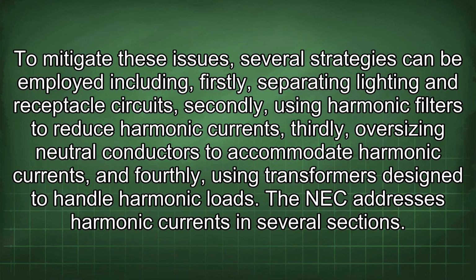To mitigate these issues, several strategies can be employed, including, firstly, separating lighting and receptacle circuits. Secondly, using harmonic filters to reduce harmonic currents. Thirdly, oversizing neutral conductors to accommodate harmonic currents. And fourthly, using transformers designed to handle harmonic loads.